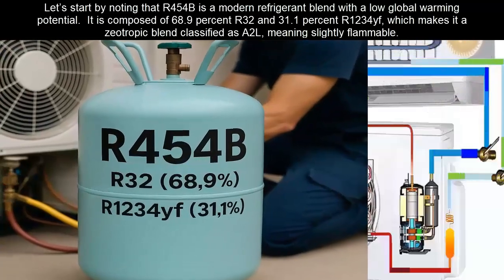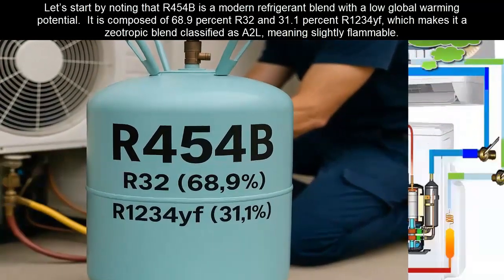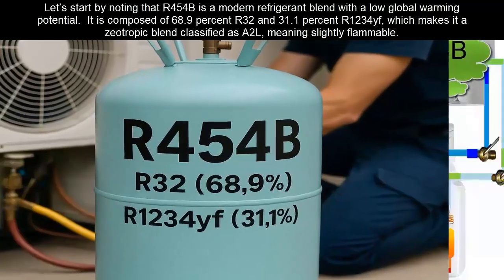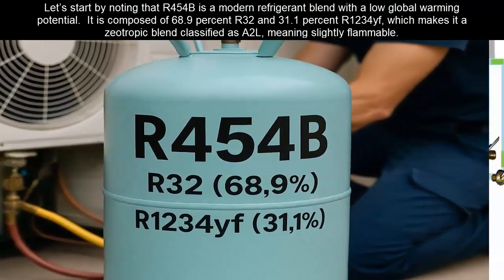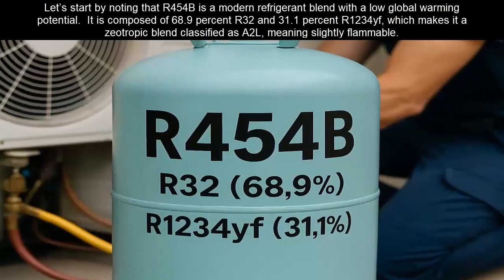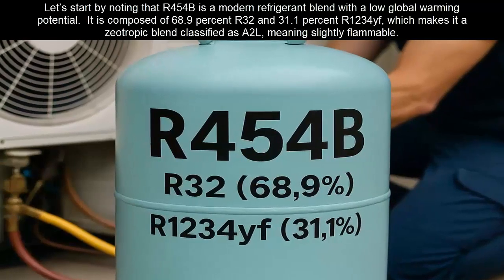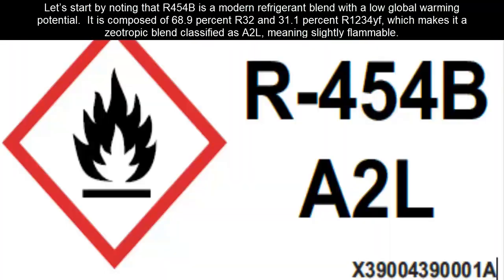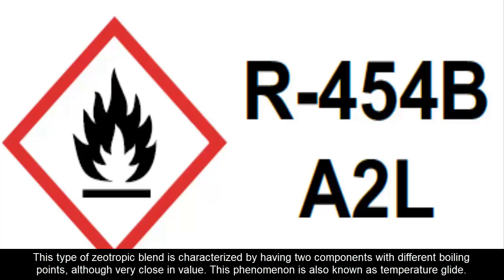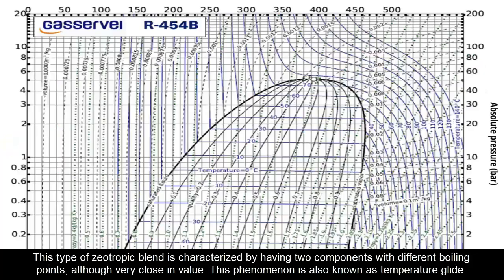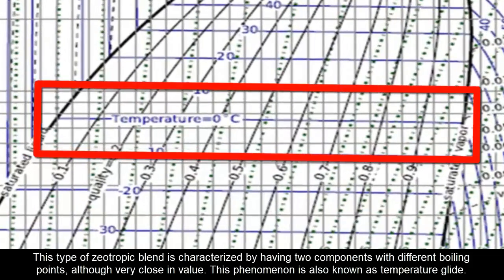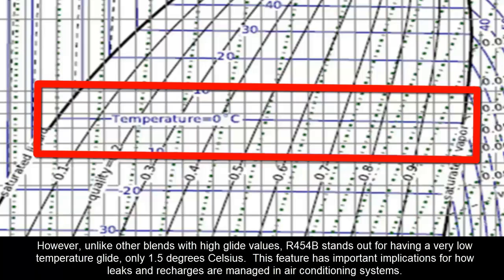It is composed of 68.9% R32 and 31.1% R1234YF, which makes it a zeotropic blend classified as A2L, meaning slightly flammable. This type of zeotropic blend is characterized by having two components with different boiling points, although very close in value. This phenomenon is also known as temperature glide.